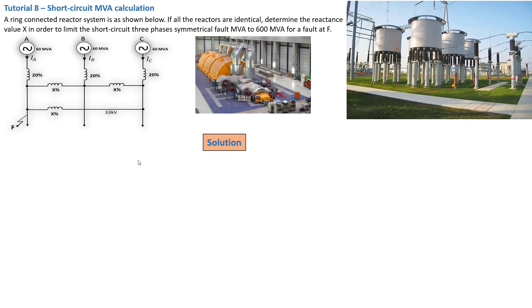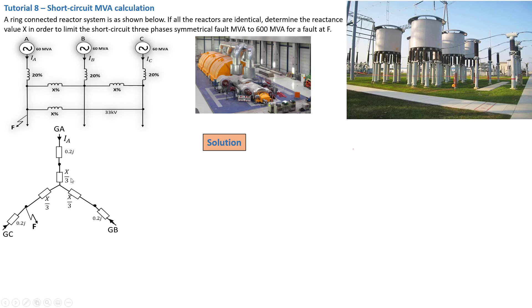We resolved that a ring-connected system is basically a delta system. We then needed to convert or transform from a delta into a star configuration. We got to a point where we had all the X% reactances that we needed to determine, and these were then replaced by X over 3 — that is converting from a delta system into a star system.